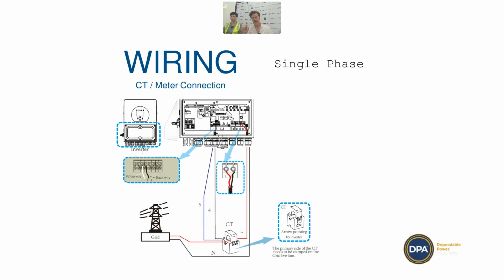The CT can be extended. It comes with a length of cable which is quite long. I think maybe it's 10 meters or something like that. But I've heard of quite a few installers now who have run Cat6 cable from the inverter to the main switchboard, like 20, 30 meters, and then they've just spliced the CT onto the end of that and put it at the main switchboard instead of running a meter, and it's worked fine. So you don't have to use the meter if you're a long distance away. You can extend the CTs, and that works perfectly fine, and it's slightly simpler.